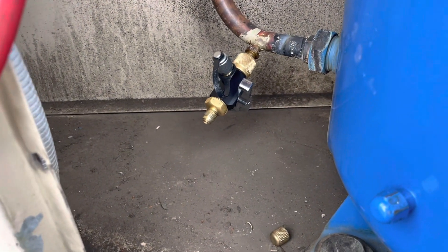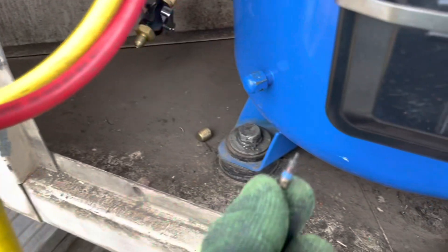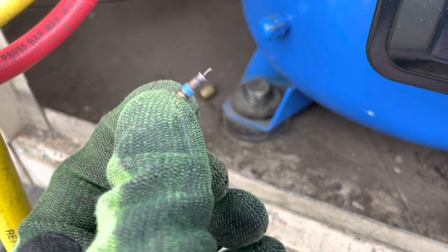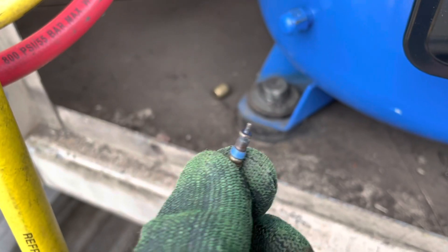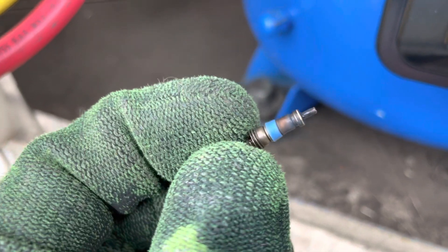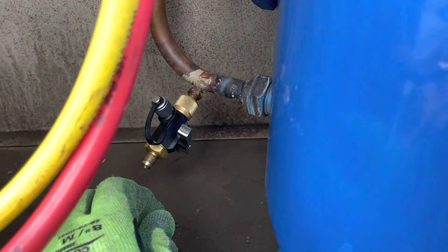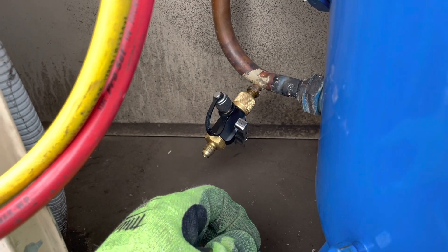In preparation for reclaiming the gas, I pulled the schrader out — look at this. It is black, man. It looks burnt. I wonder if it was leaking too. Actually, that looks like a factory fitting because there's one over here as well. Maybe they just didn't have the schrader core out when they did it. Who knows? Hopefully it's not signs of a bigger issue. We'll see how we go.